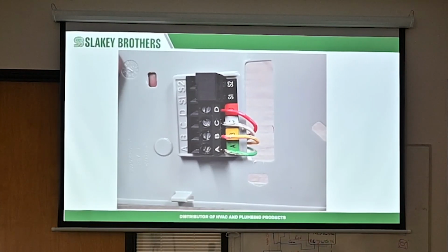If you see this behind the wall, you got to be careful of that as well. They pull out the wire, tape it up, because again, these two touching each other will create a communication fault, and obviously the common will affect the communication. Then the AC voltage here going to the DC circuit could actually short something out, so just be careful of that.